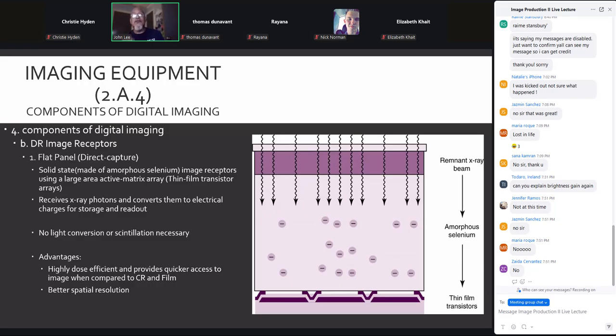Direct capture uses amorphous selenium. Again, just like the indirect capture, we are going to use a thin film transistor array. There's still going to be a thin film transistor gate. There's still going to be the detector element, amorphous selenium as opposed to amorphous silicon. And there is a storage capacitor to hold the charge until the exposure is complete.